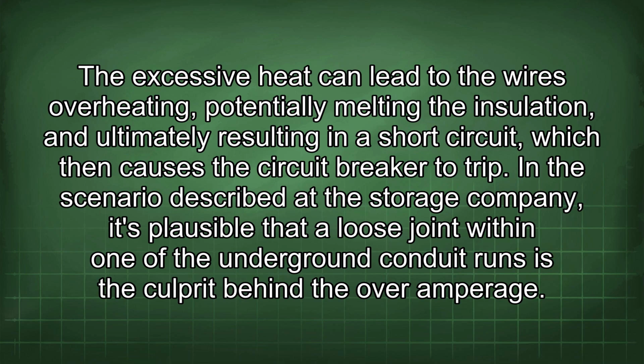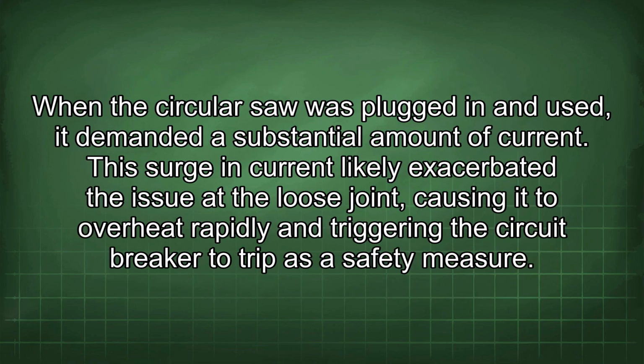In the scenario described at the storage company, it's plausible that a loose joint within one of the underground conduit runs is the culprit behind the overamperage. When the circular saw was plugged in and used, it demanded a substantial amount of current. This surge in current likely exacerbated the issue at the loose joint, causing it to overheat rapidly and triggering the circuit breaker to trip as a safety measure.